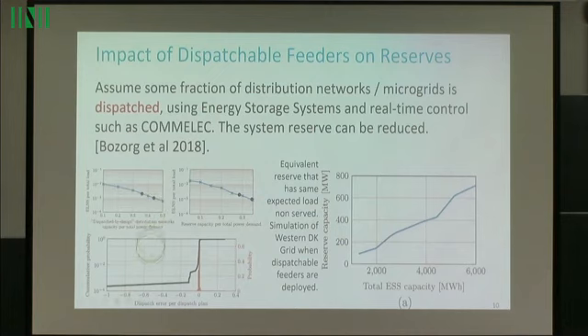Now we can do the same exercise taking into account a number of local grids that are dispatched because they have a real-time operating system like the one shown here. Of course, the dispatch plan is never implemented exactly, so we took statistics from our grid, which has been operating for over a year, on how well we followed the dispatch plan, and assumed other grids would do similarly. Based on that, we computed the amount of reserve—the regulating power—needed to achieve a certain quality of service measured by expected load non-served. This shows that, as expected, depending on the penetration of dispatchable feeders, the amount of reserve needed is highly reduced.